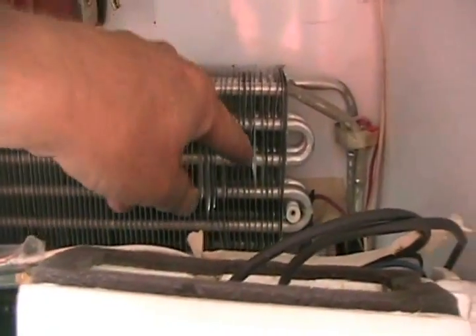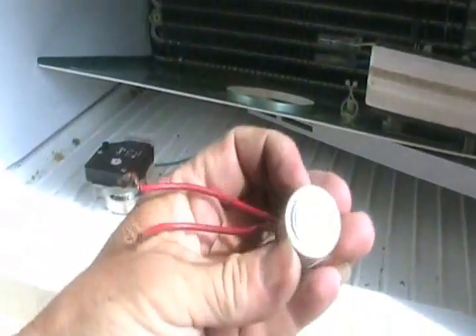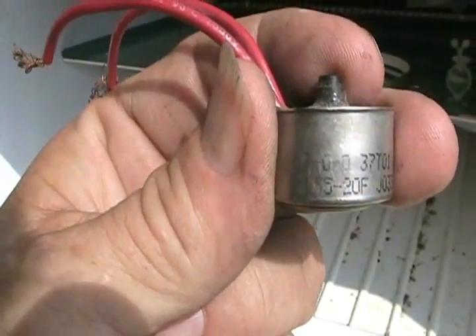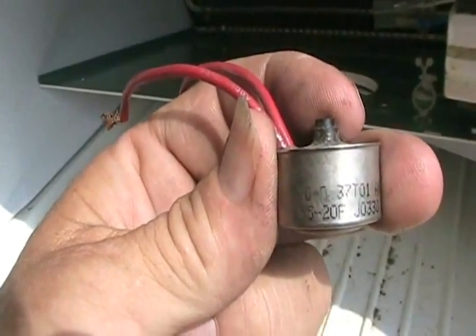Somewhere on the upper part of the cooling coil is this little disc-shaped thing with two wires — that's called the defrost termination thermostat. As you can see, they have numbers: 55°F is when it opens the circuit and shuts off, and 20°F is when it closes and turns itself back on. I'll explain that later.